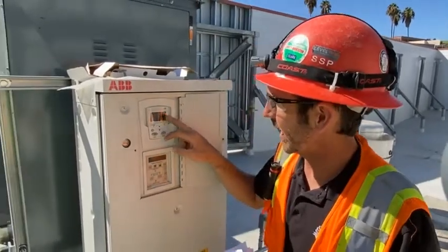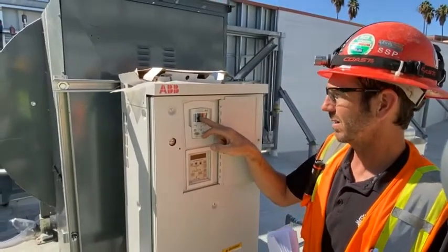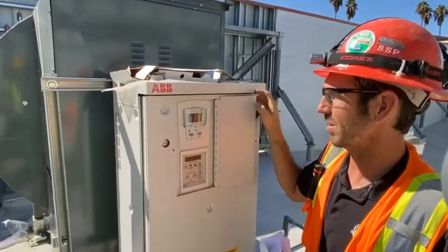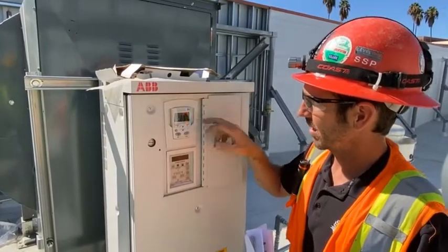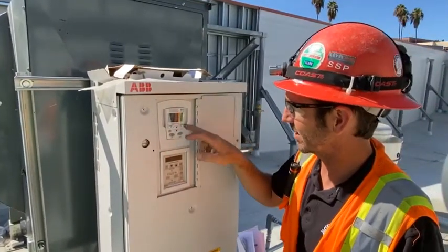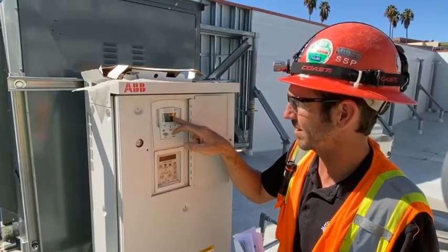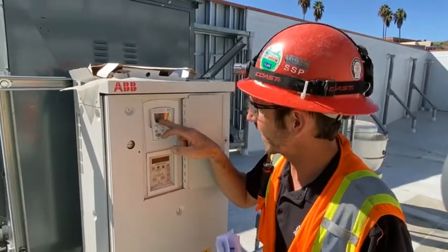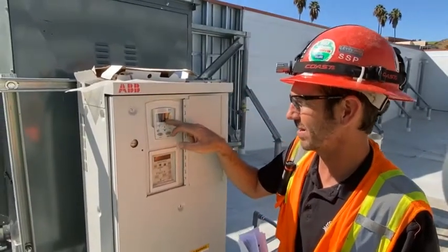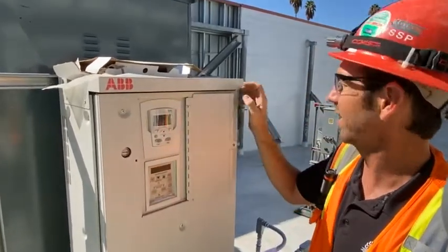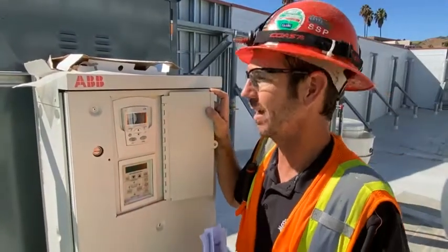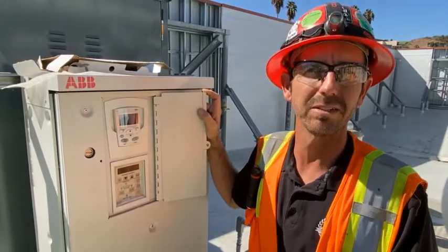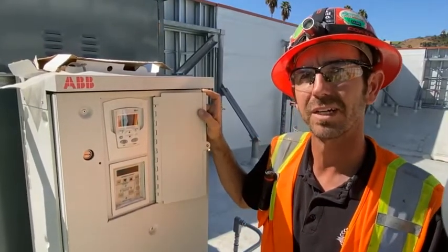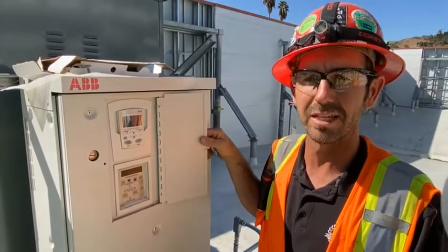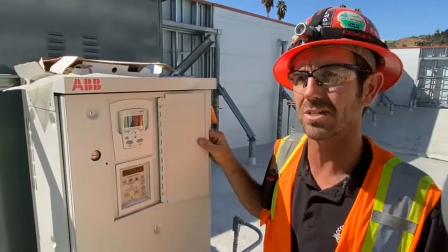At the top display, we have percent speed, which is out of the maximum, the percent speed out of 60 hertz, so it'll always be the same number. Then it gives you an amp readout. This lower display is currently volts DC. We're not using an external speed signal, so that will always be 0. In the future, if you want a different readout, it can be changed in the display parameters, which is 34.